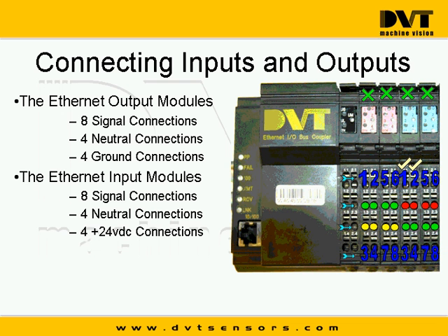We go to number 2, and then we make our way down below to number 3 and 4, and then we start back at 5, 6 up top, 7, 8, and we finish off the input module. However, you should notice that the neutral connections are on the bottom half of the input modules. Okay? While the signal, or the 24 volts that might be necessary to power the input properly, depending on what type of connection you're making to the input, is on the top.